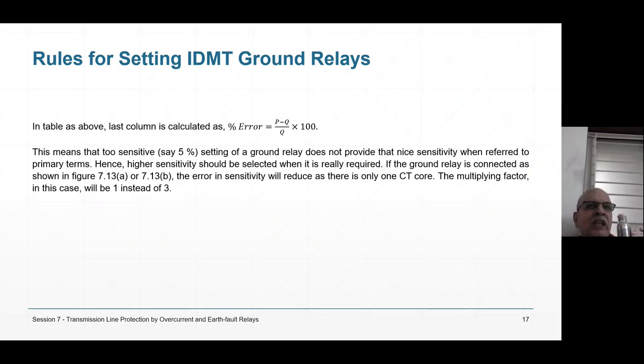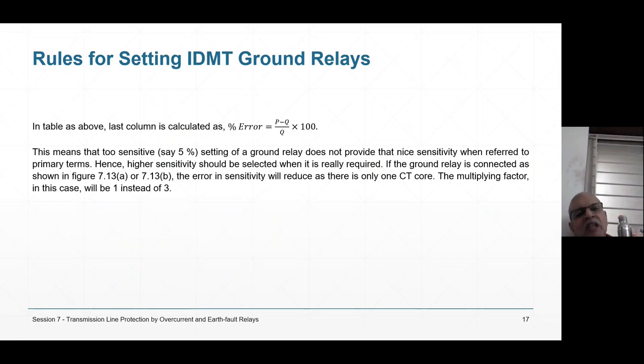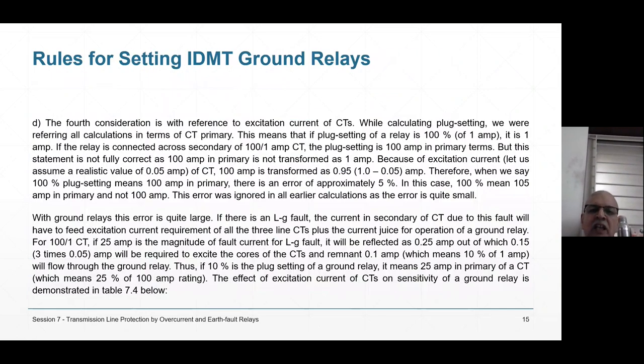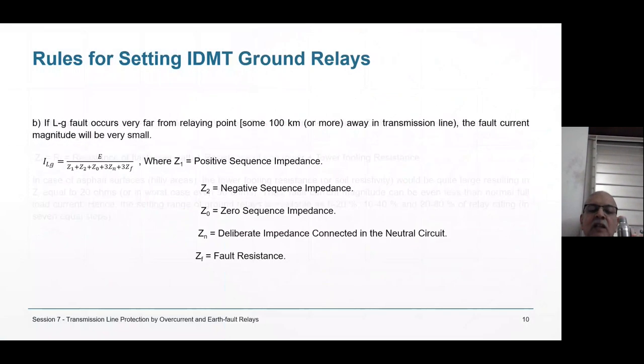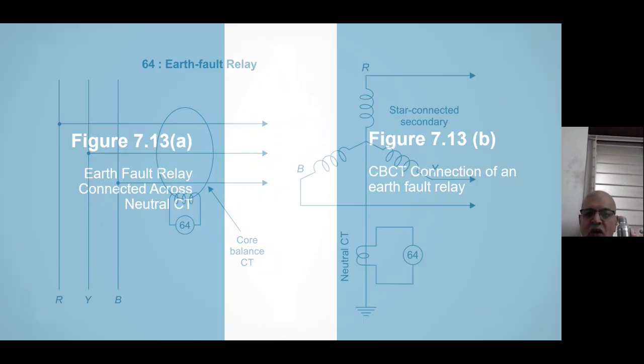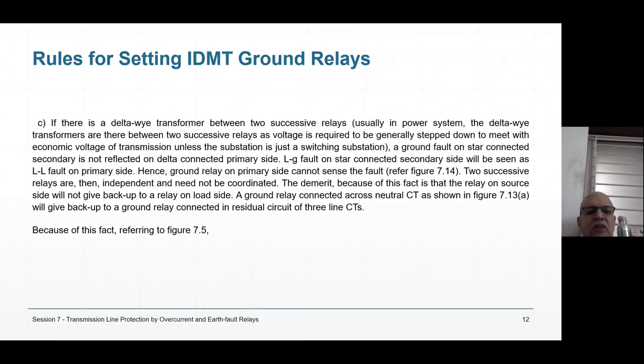The relay current is three times worse if you connect three CTs in residual. If you use a CBCT or a neutral CT, there is only one CT, so that multiplier of three is eliminated, and the relay can be made more sensitive with those connections.